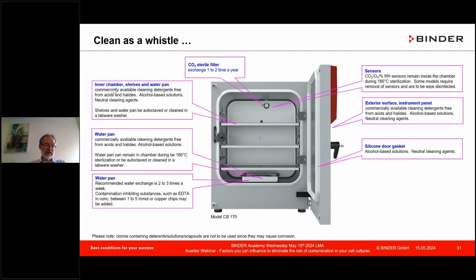And sensors. Many sensors, CO2 sensors, oxygen sensors, if you have a CO2 or so-called tri-gas incubators there, as well as the humidity sensor, they can be sterilized at 180 degrees C. They remain inside and everything is actually clean as a whistle for your next setup. So that's also something to consider. And naturally 180 gold standard nowadays.